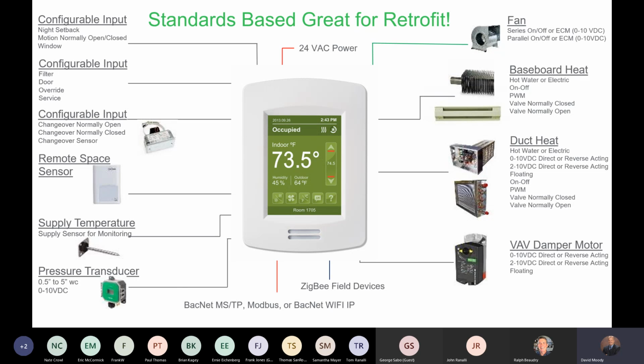We've had somebody that uses a 1/2 volt to 3.5 volts. You can make that work, but it does eat up one of the additional inputs on the room controller to make that work. So what you really want to do, the message here is stick with 0 to 10 volts, right?